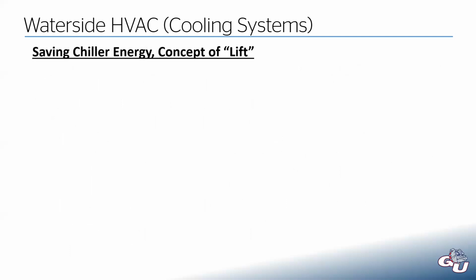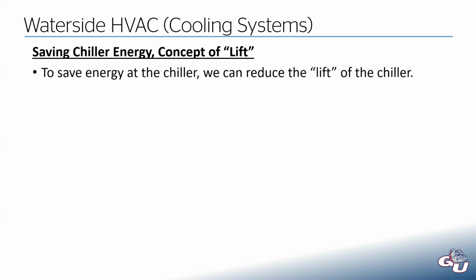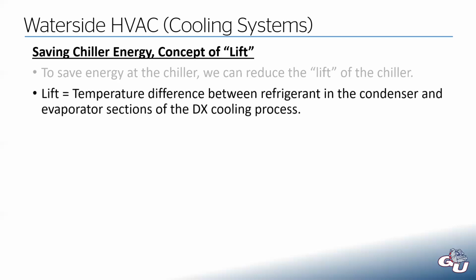So let's talk about lift, which is another concept we're piggybacking from back when we talked about heat pumps. If we're going to save energy at our chiller, we can reduce the lift of the chiller. Lift is the temperature difference between the refrigerant in the condenser and evaporator sections of the DX cooling process. I'll have a refrigerant graph here in a moment, but remember the refrigerant process is a somewhat rectangular process on the pressure enthalpy chart.